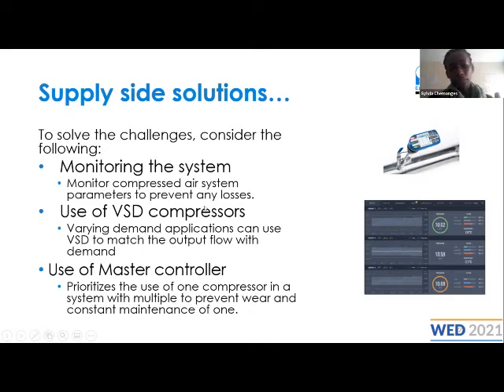For systems that have more than one compressor, let's say 2, 3, 4, 5 compressors, you need to have a master controller. This is a device that helps prioritize which compressors run depending on the performance that's required at the plant. So if you have 3 compressors and your load increases, let's say from 30 to 40, this master controller will figure out which compressor I need to run to be able to generate this much compressed air within the system. So having a master controller helps a lot for most companies that have around 3 compressors or more.